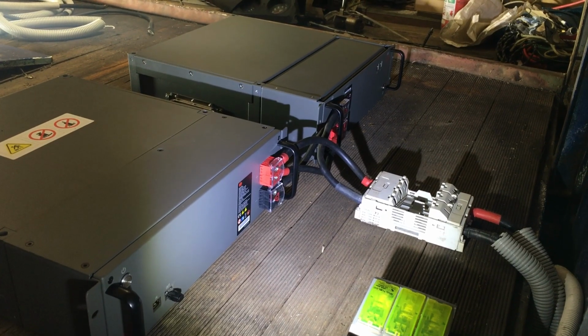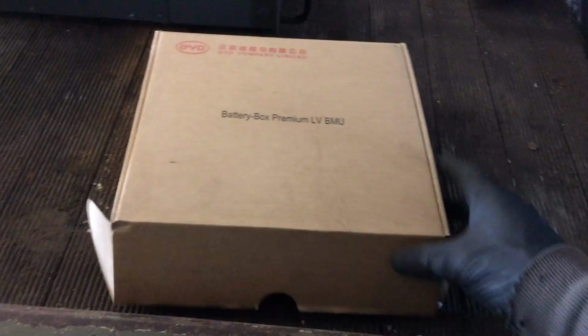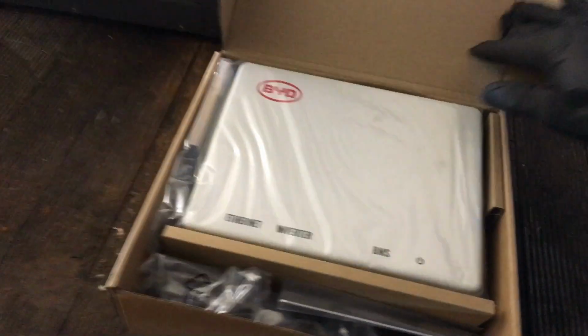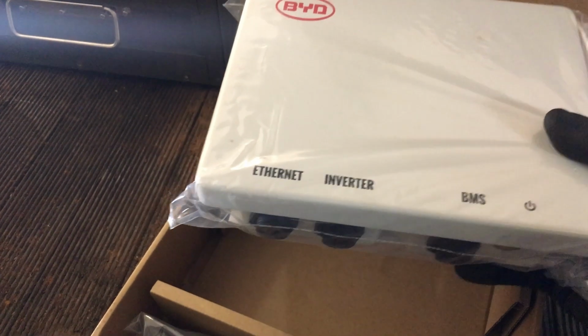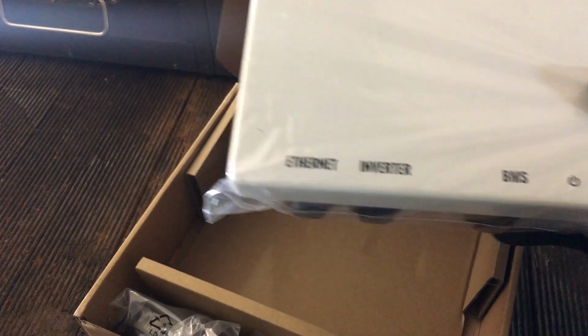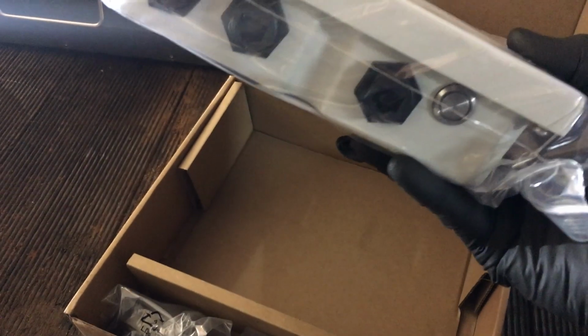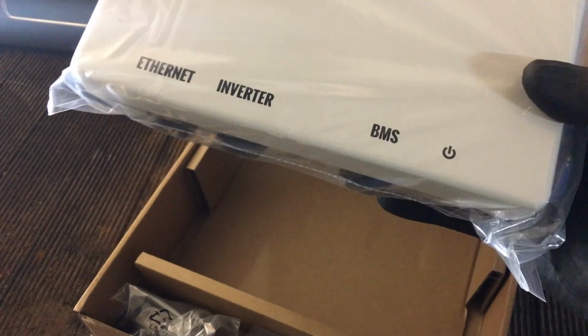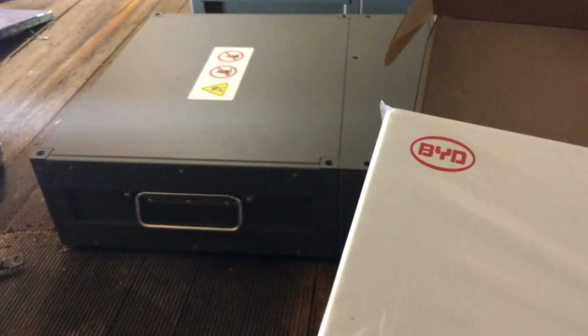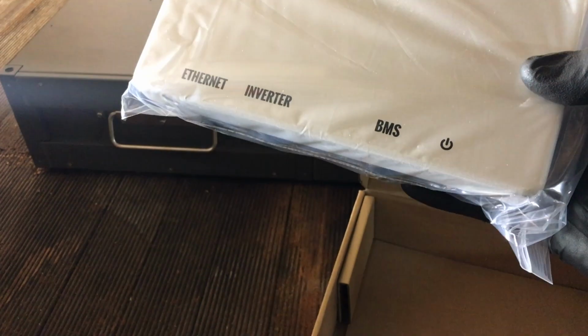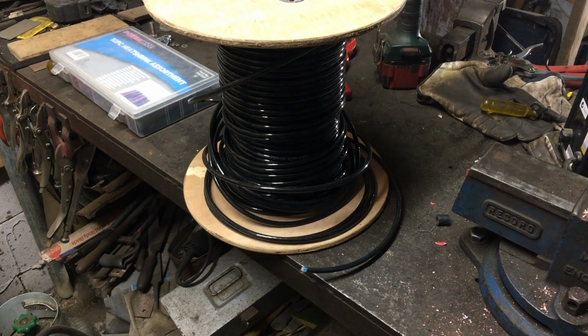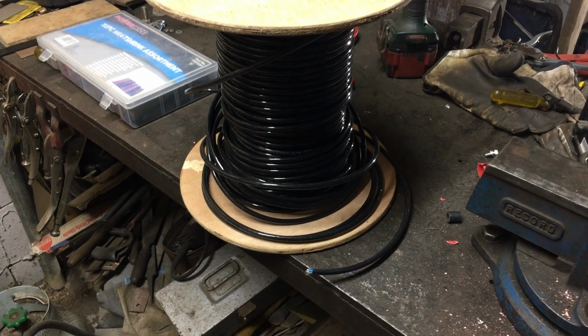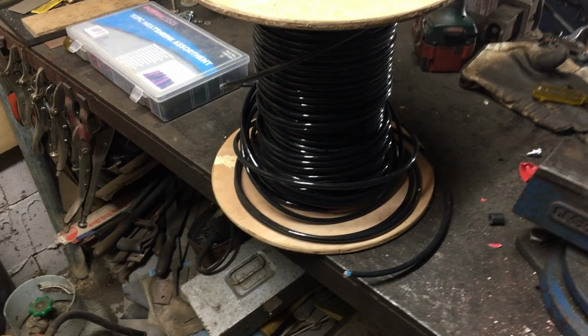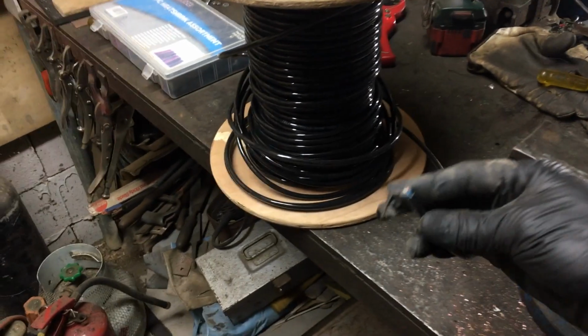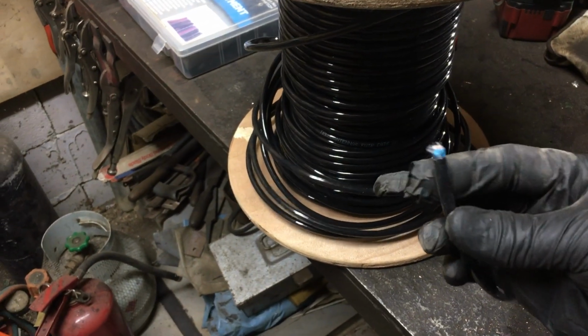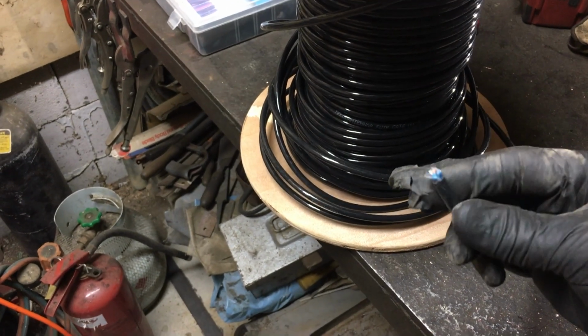Righto, we've got the battery cables hooked up. This is the low voltage battery management unit, so where it says inverter, we've got to hook that up to the Venus. Ethernet is for internet so it can update itself, and the BMS goes to these modules. We need a standard Ethernet cable for the BMS cable, and the inverter cable needs to be custom. We have to run an Ethernet run from the battery box to the BMU, because we're going to mount the BMU in the cab. I want to do that out of good quality Ethernet to keep it shielded, so this is a shielded Cat 6.